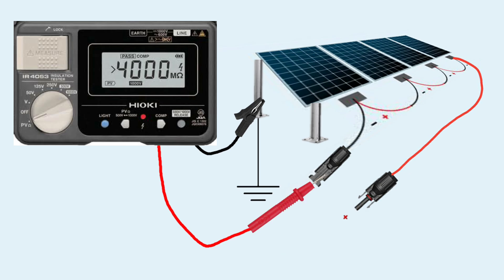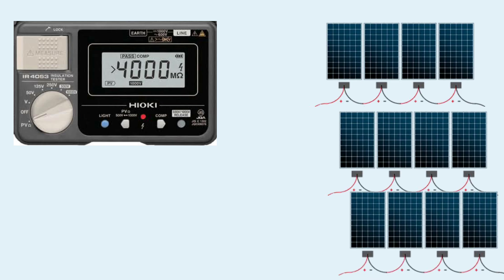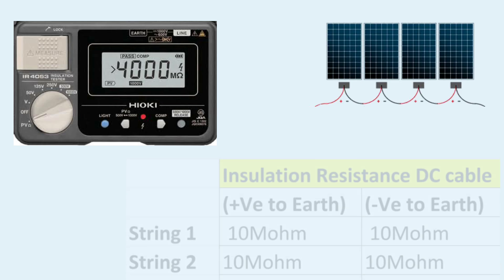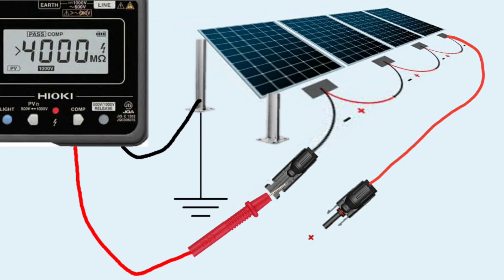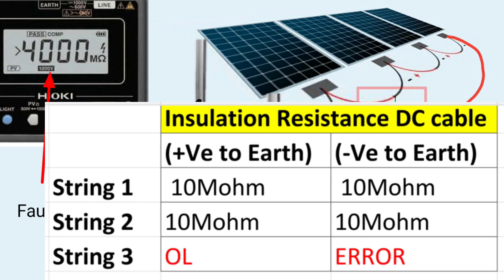Similarly, test the IR value between the negative terminal and earth — but only if the previous IR value between the positive and earth has passed. Test all strings in the same manner to get IR values between positive-to-earth and negative-to-earth for multiple strings. If any cable is tampered with, cut, or damaged, it will be caught in the test showing lower values and failing.